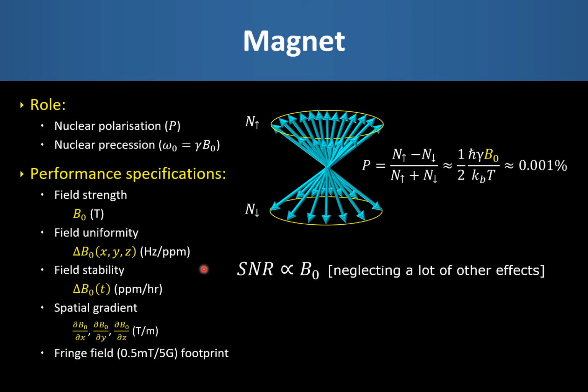The uniformity of the magnetic field is also very important in terms of the dephasing of the transverse magnetization, so we need to ensure that the field is as uniform as possible. The field also needs to be quite stable over time, so whatever method is used to generate the magnetic fields, it needs to have a very good level of temporal stability. We also need to consider the spatial gradient of the static magnetic field. This has nothing to do with the gradients that create the images. This is the variation in magnetic field that falls off with distance from the magnet, and it is this variation in field with distance that is responsible for the projectile effect of ferromagnetic objects that may be inadvertently brought into the MR environment.